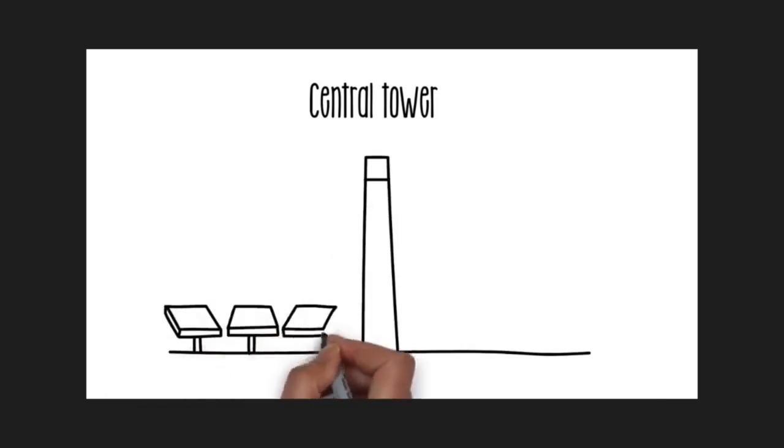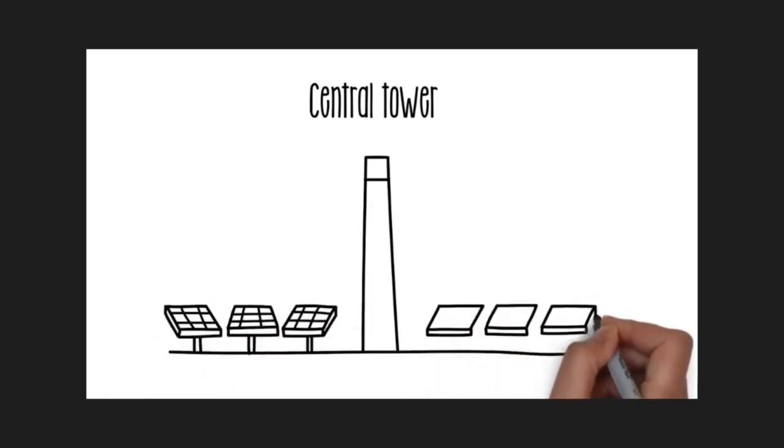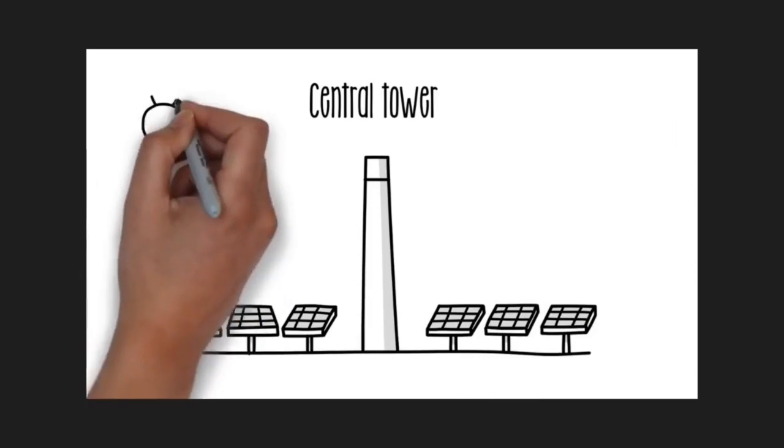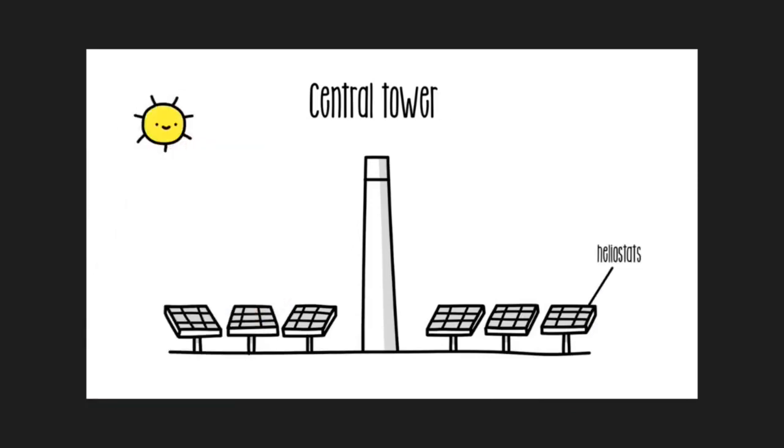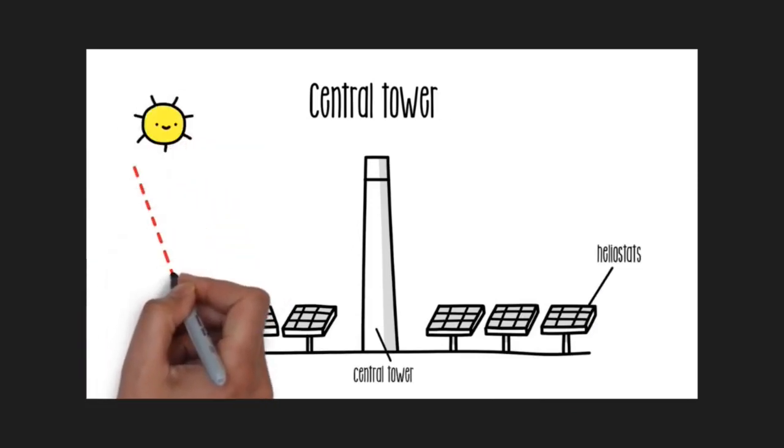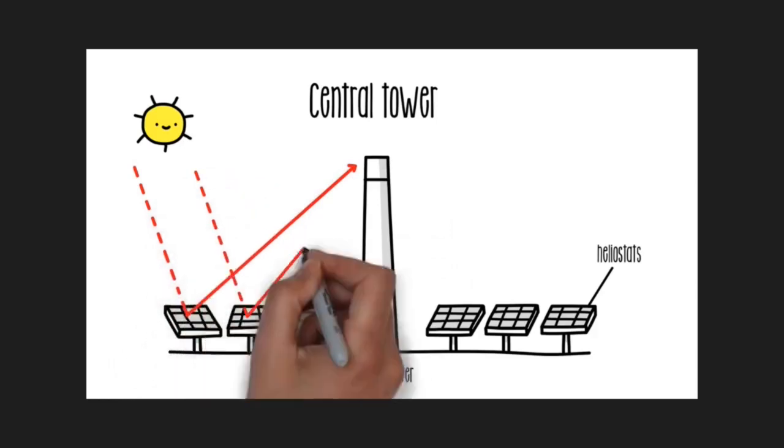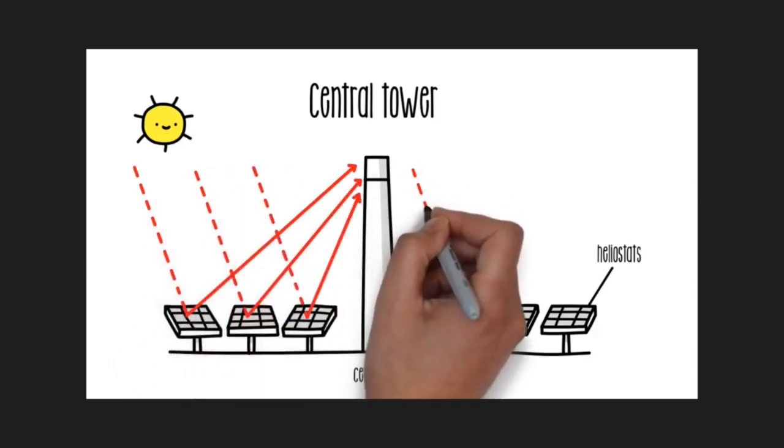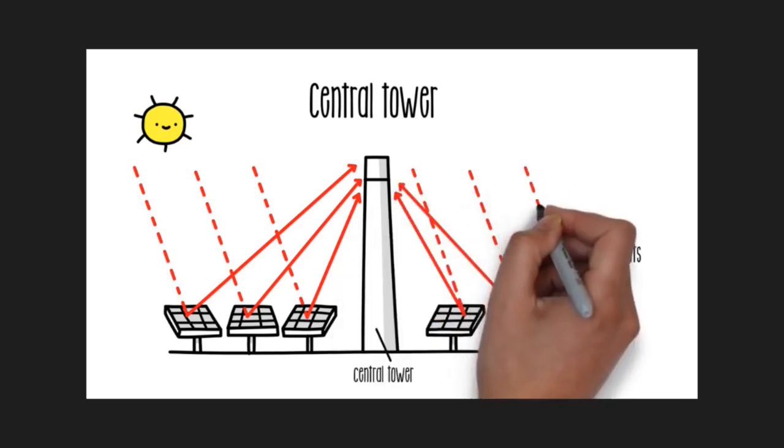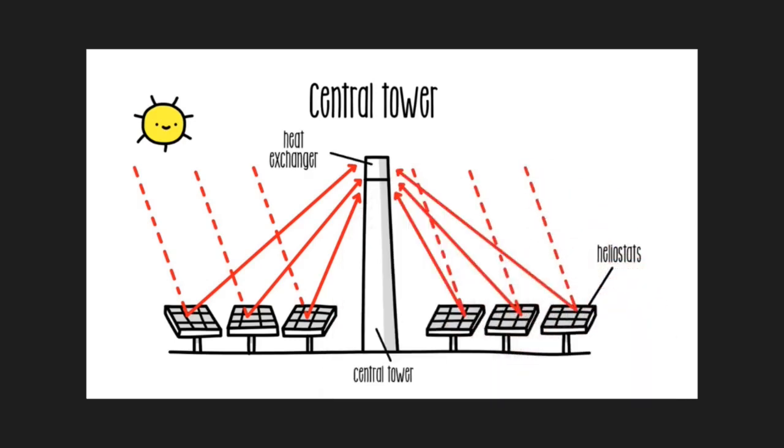Central tower technology concentrates the radiation at a point and requires no fluid circulating in the solar field. These facilities have a field of heliostats - flat mirrors that reflect the radiation onto a central tower with heat exchanger located at the top. The mirrors can be oriented according to the position of the sun. With this technique, temperatures of 600 degrees Celsius are reached.